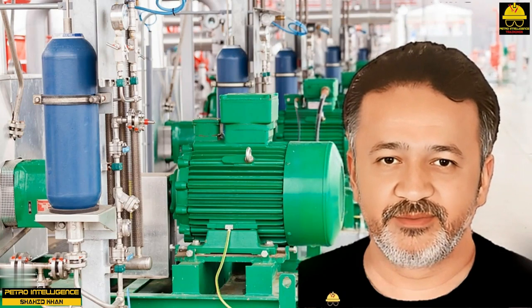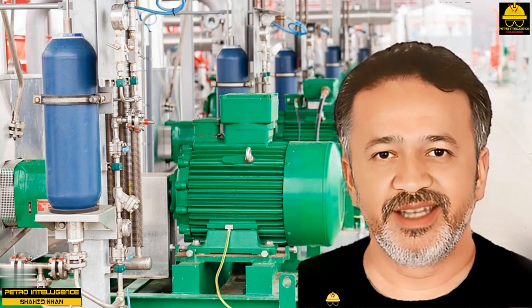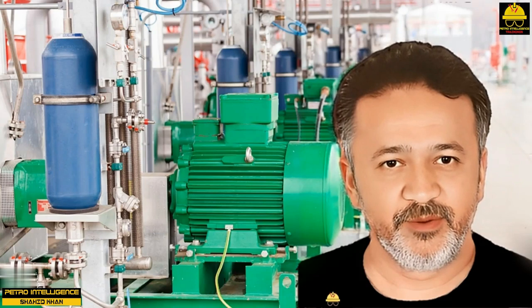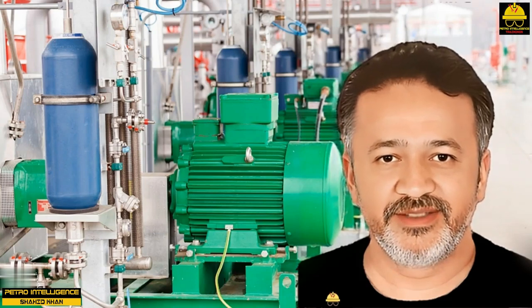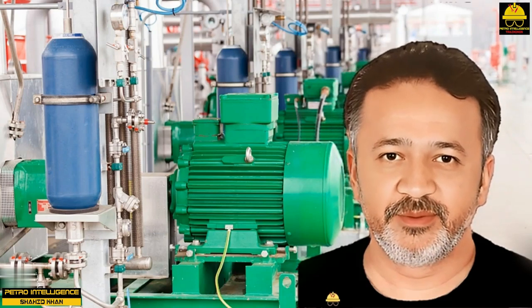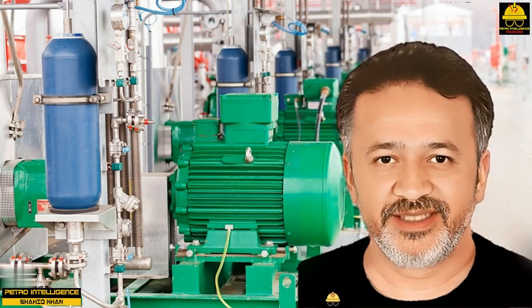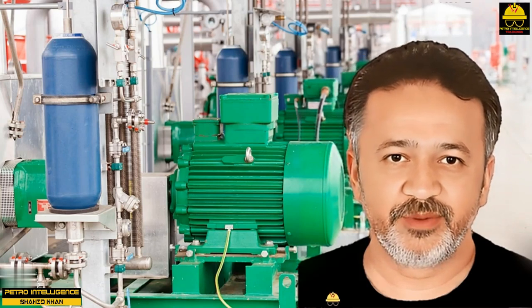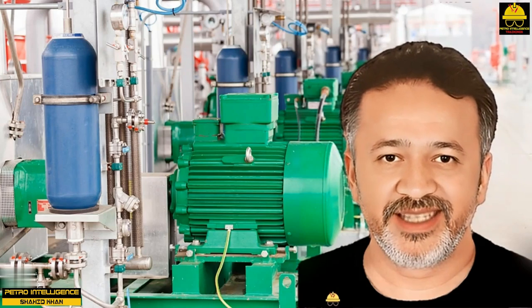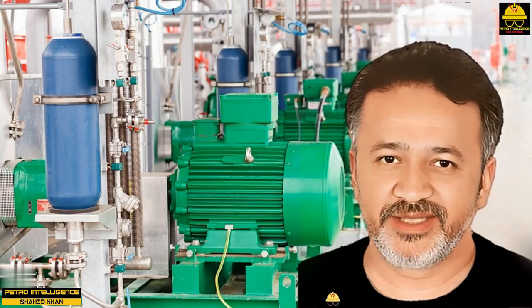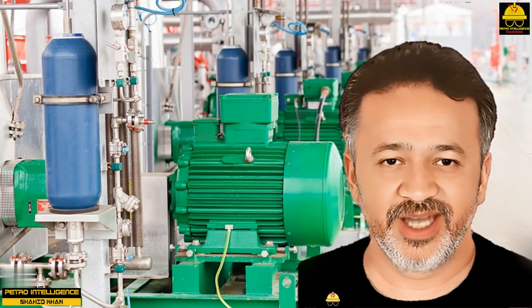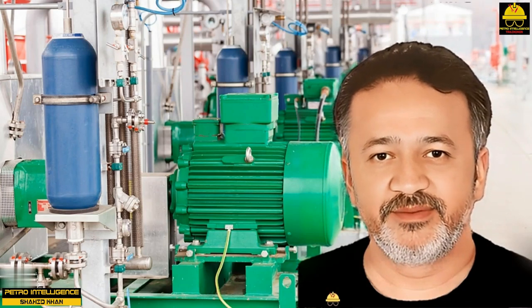Affinity laws. Relationships, called affinity laws, exist among a centrifugal pump's speed, capacity, head, and power. The capacity of a centrifugal pump is linked directly to its speed, or RPM. Total head is proportional to the square of the speed. Consumed power is proportional to the cube of the speed.